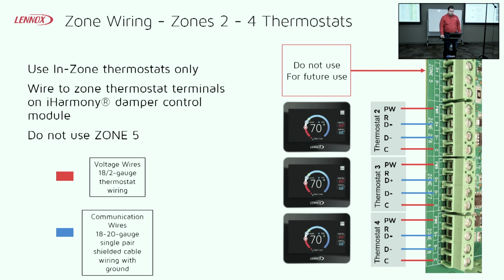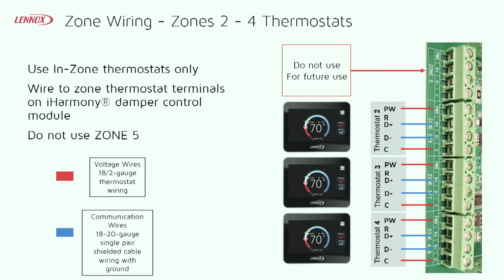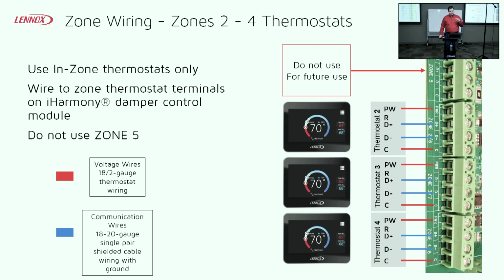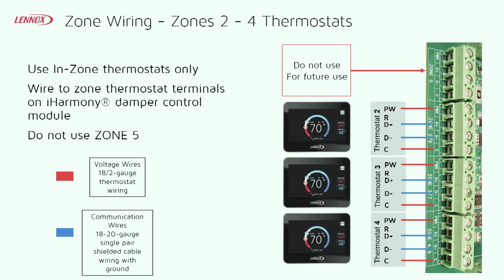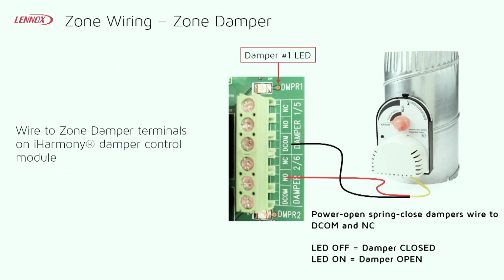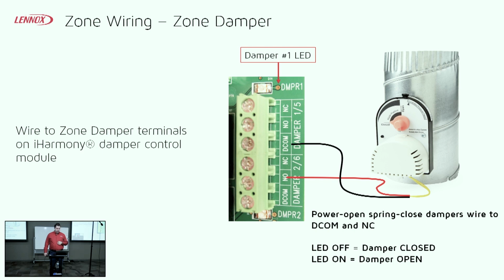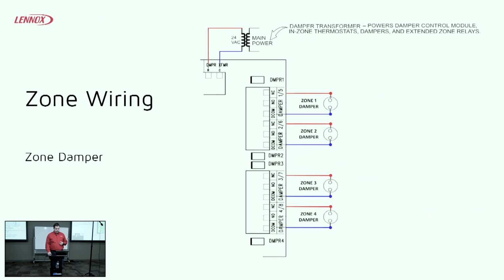So again, this is our zone stat wiring. Again, zone 5 we're not going to use. It's a dead panel, a dead terminal. Since this is all DC, again, running 2 wires is going to be your best option to prevent issues. It's a little bit less critical in these scenarios where we're just dealing with DC. I haven't seen as much issue communicating, but that can be a good thing to use. Again, your damper wire is just going to be 2 wires. It's very, very basic wiring there.